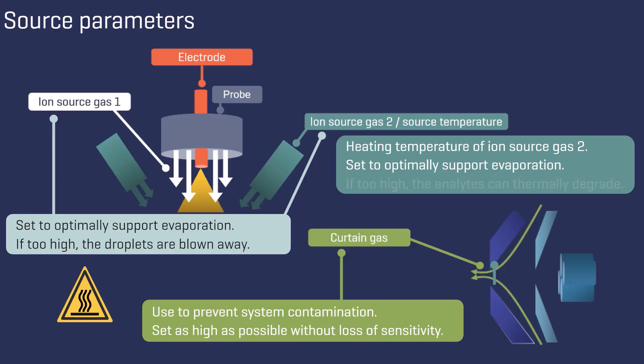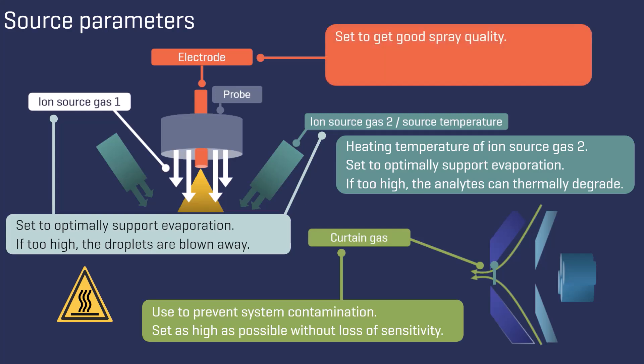However, if the temperature is set too high, there is a risk of thermal degradation of your analytes. The spray voltage is applied between the electrode and the entrance of the mass analyzer and should be set in a way that you will have good spray quality.